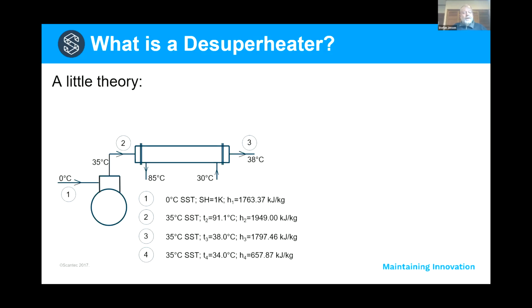The enthalpy is shown. Once the gas has been compressed, it reaches condition 2. You can see the temperature's gone up to 91 degrees and the enthalpy has increased. Then condition 3 is downstream of the desuperheater. There we have taken the superheat of the ammonia gas out, or any gas. So that is the process that happens in the desuperheater. We desuperheat the refrigerant gas coming out of the refrigeration compressor to a point that is close enough to the saturation point. In other words, just before the refrigerant starts to condense.